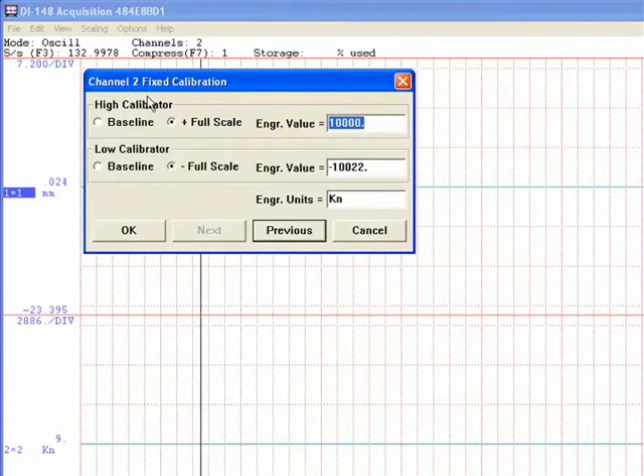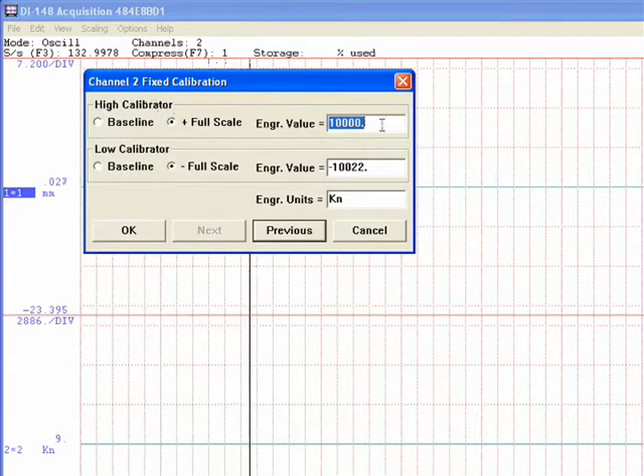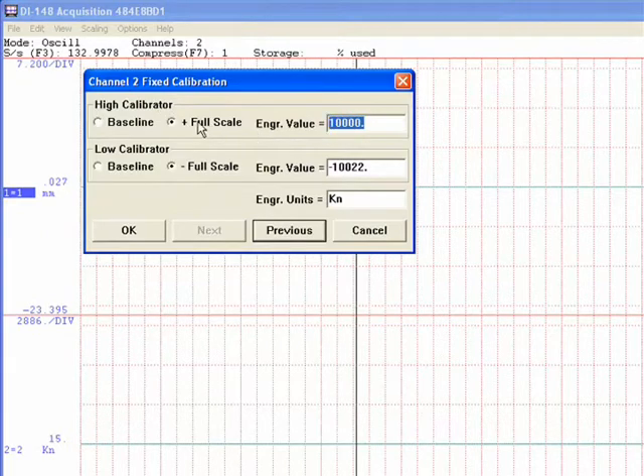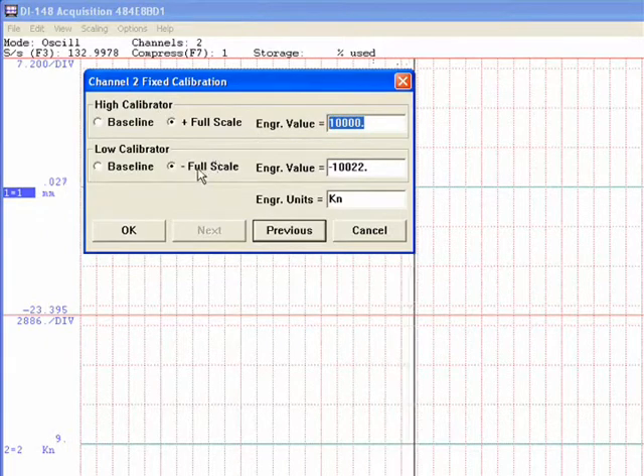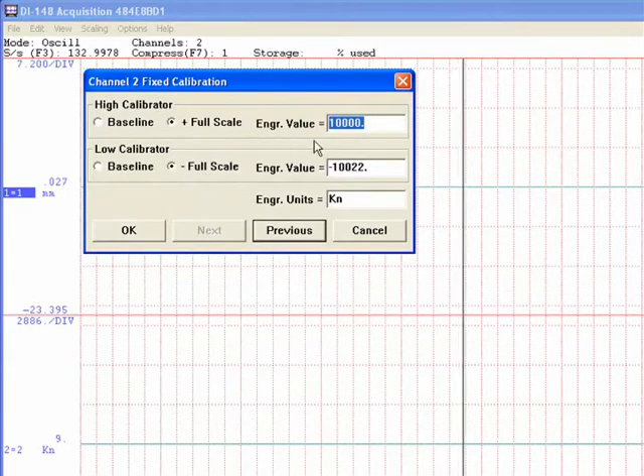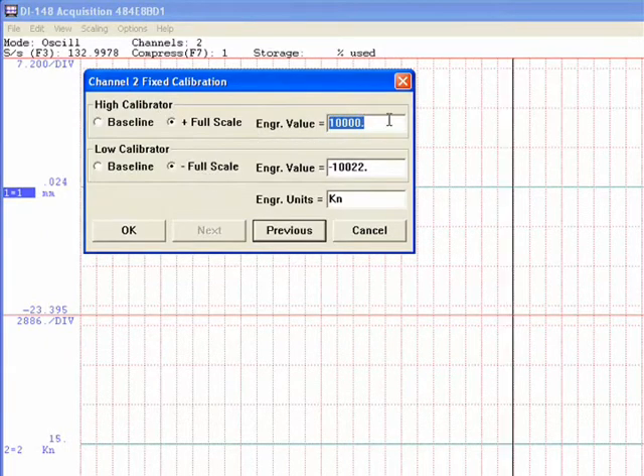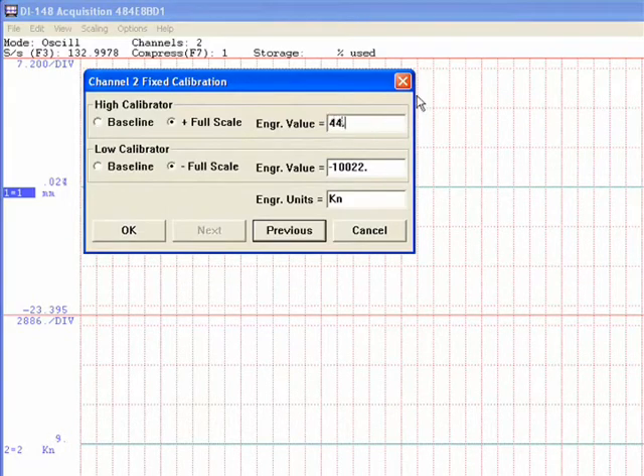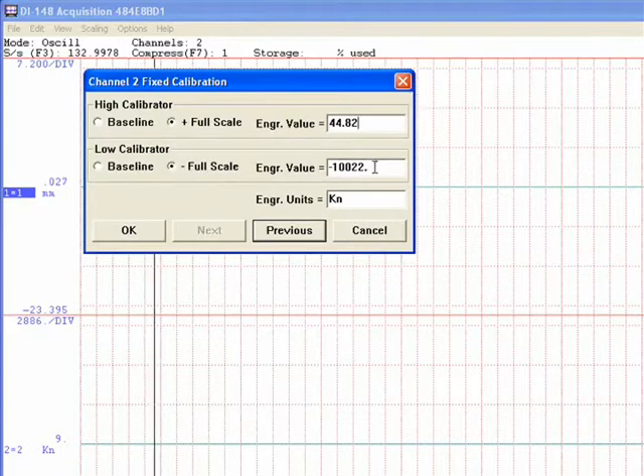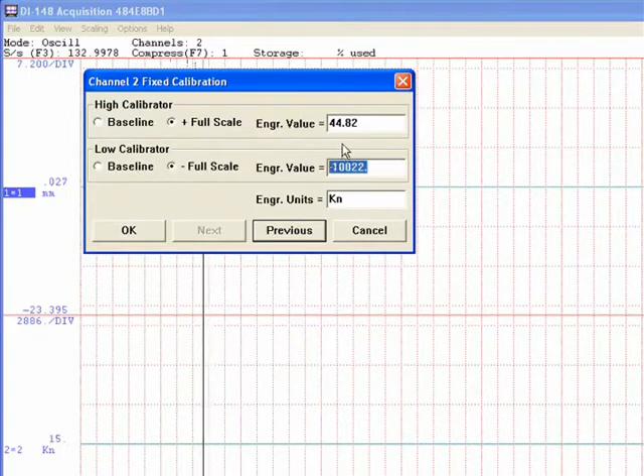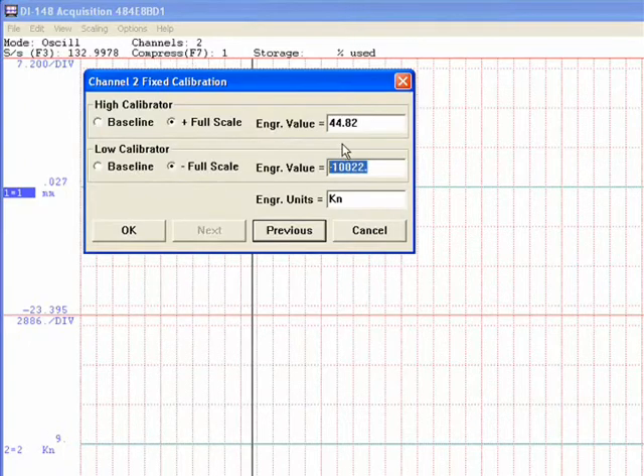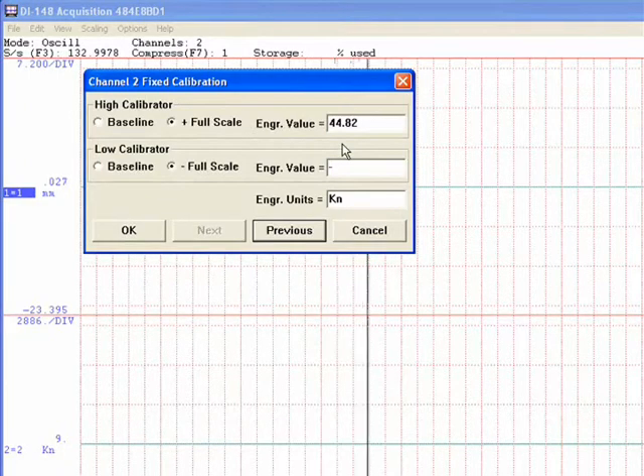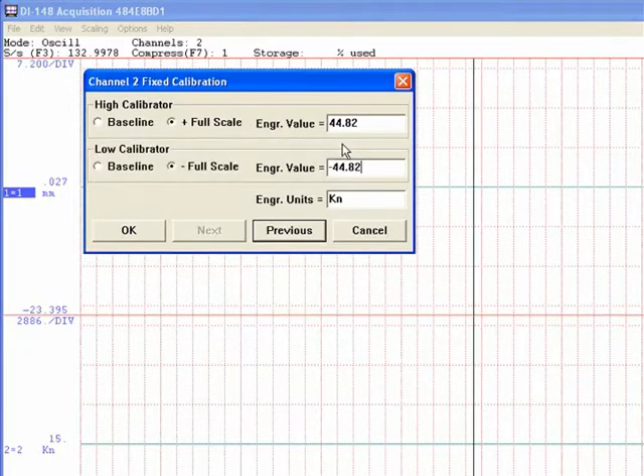You will go to channel two. Make sure it says full scale and negative full scale. This is your load. We're going to put in 44.82, and negative 44.82.